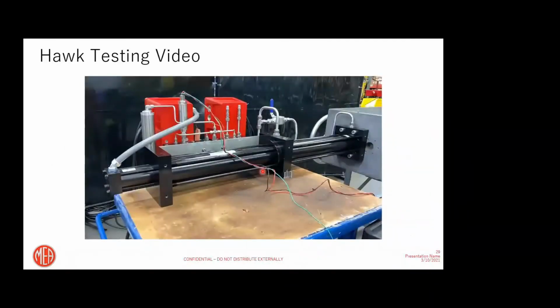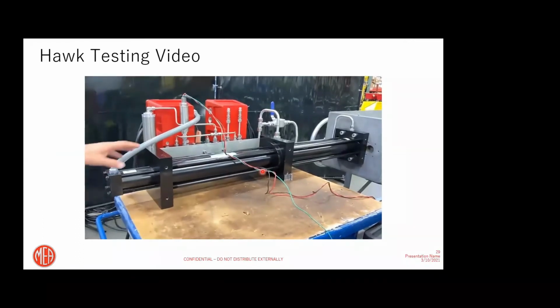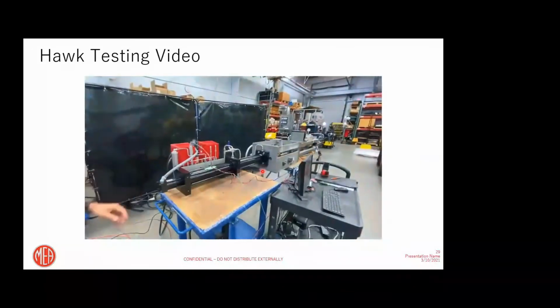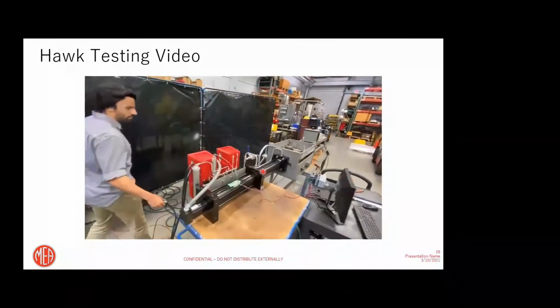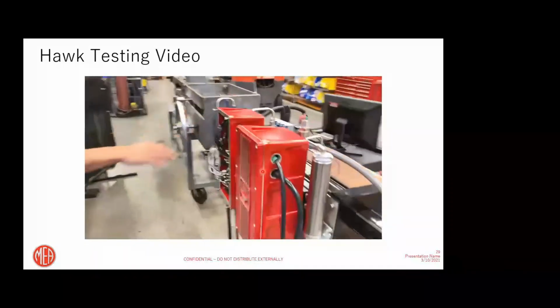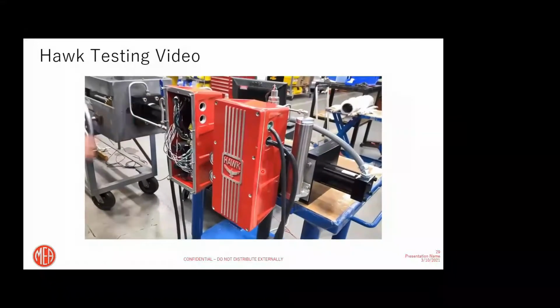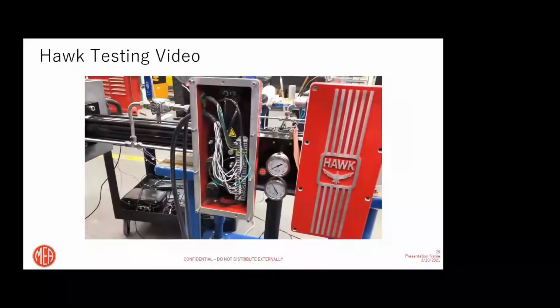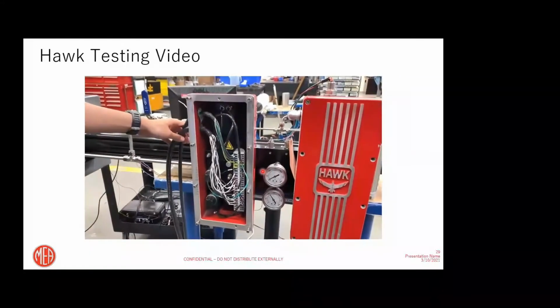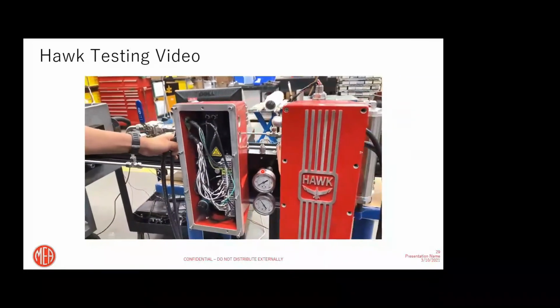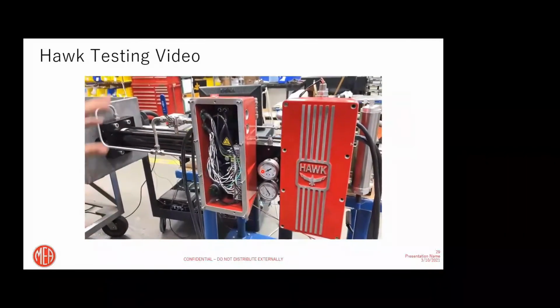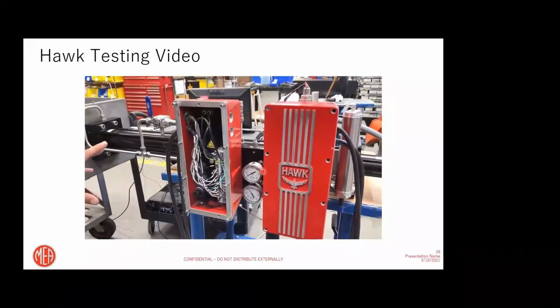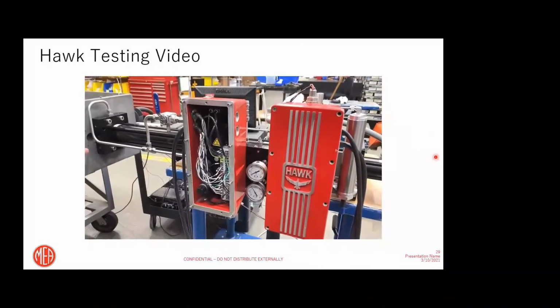So here is a video of the actual test setup and some positioning accuracy. You'll be able to see what we actually did, so please watch the video. The actuator cylinder is currently coupled to a loaded valve simulator. On the front here, we have the dual HPS system, one with the cover on, and you can see the HPS with the cover off, where we've got a motor that's coupled to a pump. All of that is going to be controlled by the drive that is connected to this HPS via the field wiring that you see. This particular configuration is for testing only, but it still simulates exactly how to drive the actuator.